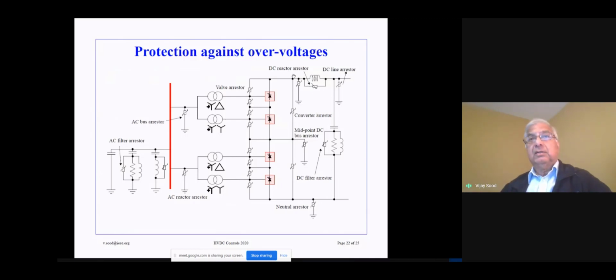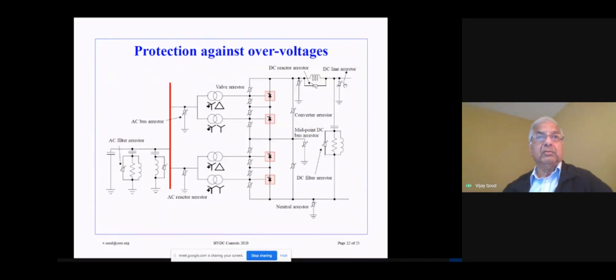The DC arrestor, there's a reactance, there's a voltage arrestor across that one. There's a DC line protection system. There's an arrestor across the DC filter as well. And then if there's a neutral, the midpoint arrestor and the neutral arrestor will be there. So various arrestors are utilized against overvoltages, and these are all shown over here.